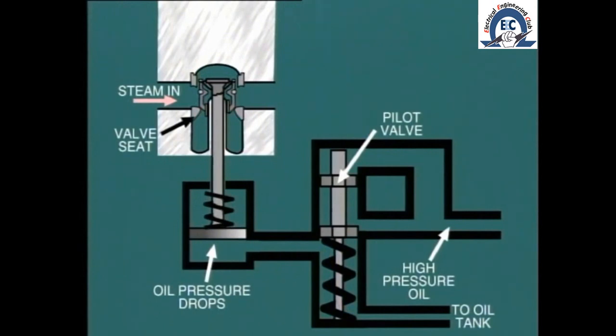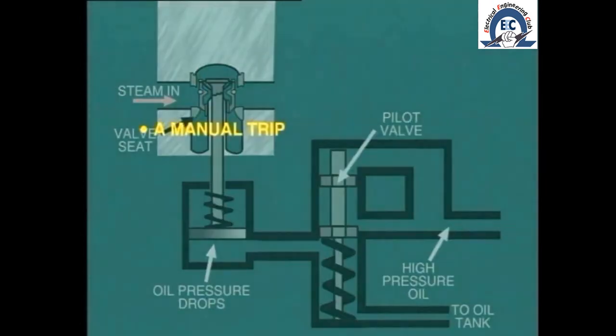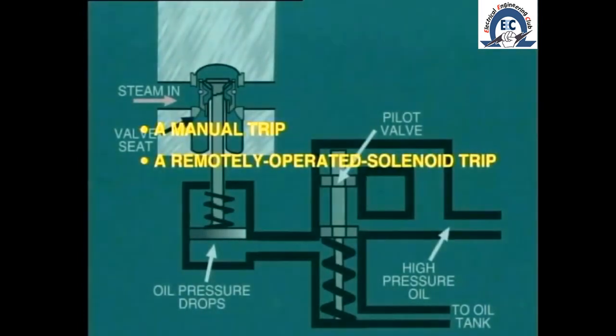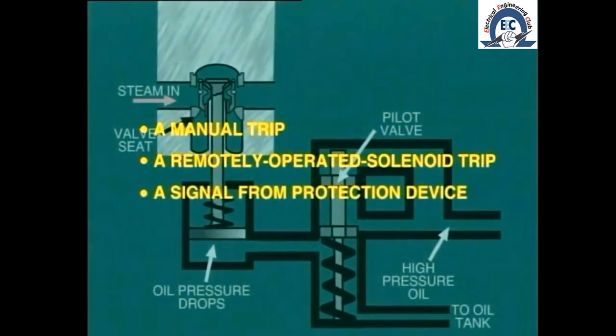As we'll see later, operation of the pilot valve, or trip valve as it is known, can be achieved by any one of several alternative means, including a manual trip, a remotely operated solenoid trip, or a trip signal from various protection devices.